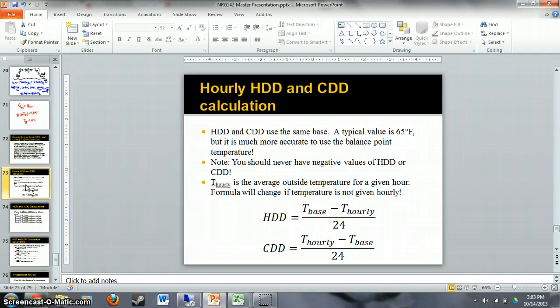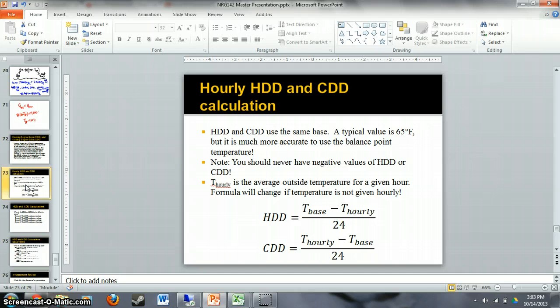First, we're going to use the same base for heating degree days and cooling degree days. A typical value is 65 degrees, but as we discussed, the balance point temperature is much more accurate if you can find it for your building. Also, a big note: you should never have negative values of heating degree days or cooling degree days — we'll see how to correct for that.